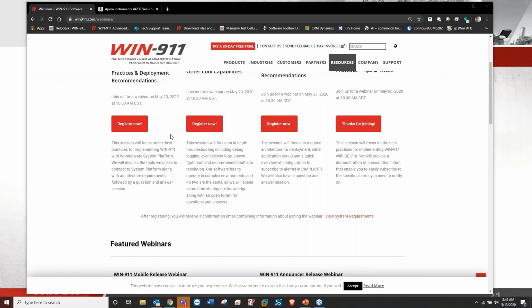If you want to be a little more specific, Kari, about that, we can try to answer it better. Yeah, I think that's something. This is Steven Rivas, the product manager at WIN-911. I think it's something we should start a support ticket for, and then we can get to the root cause of it. If it's working for a while, then it stops working, there's likely some access permission or access issue through MX access that we're having, and we need to get to the bottom of that to resolve it.